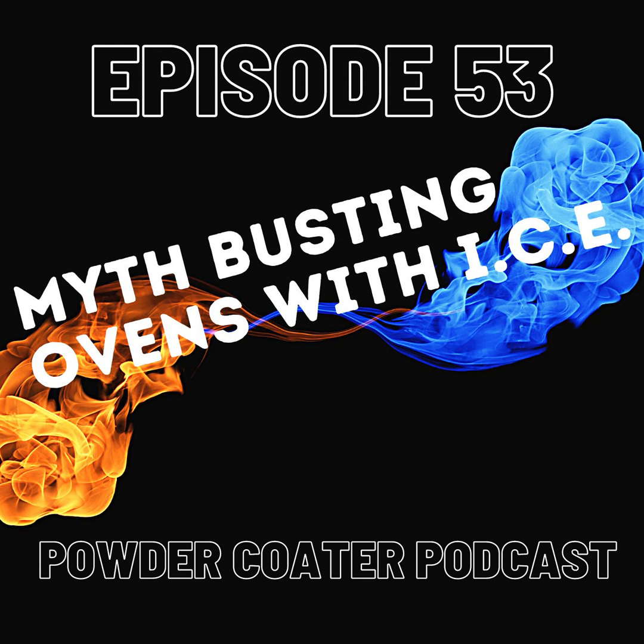The thing that we try and avoid the most is, because I've seen a lot of ovens where they'll have both the supply and the return in the ceiling. So what happens is now you just short circuit. The lower section of your oven tends to be cooler by a number of degrees because you're dumping it in. And unless you have a really high velocity fan, you can't blow it all the way to the floor and then ask it to come back up to return.